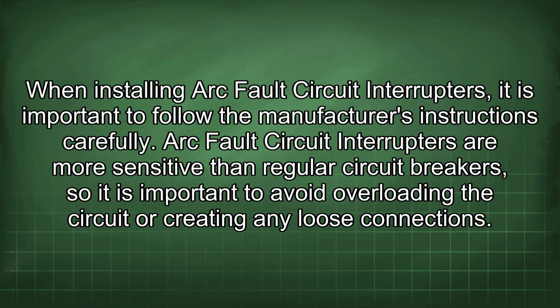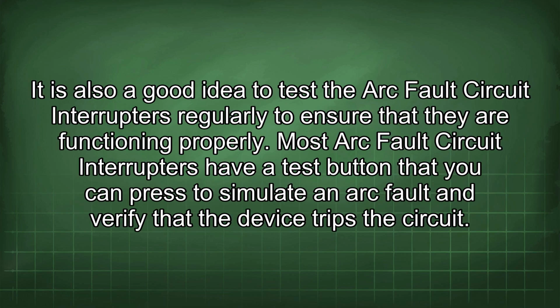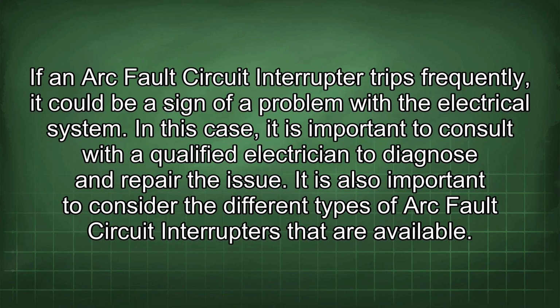When installing arc fault circuit interrupters, it is important to follow the manufacturer's instructions carefully. Arc fault circuit interrupters are more sensitive than regular circuit breakers, so it is important to avoid overloading the circuit or creating any loose connections. It is also a good idea to test the arc fault circuit interrupters regularly to ensure that they are functioning properly. Most arc fault circuit interrupters have a test button that you can press to simulate an arc fault and verify that the device trips the circuit. If an arc fault circuit interrupter trips frequently, it could be a sign of a problem with the electrical system. In this case, it is important to consult with a qualified electrician to diagnose and repair the issue.